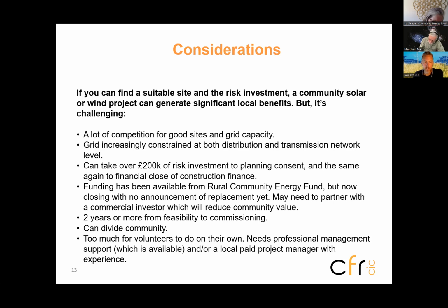There's a significant challenge in the way the grid queuing system works. If you're a community scale project connecting at 11,000 volts or 33,000 volts, you have to first go through the distribution application process and secure a connection, paying potentially a significant deposit to secure it. Only after you've accepted that connection does the distribution network operator - UKPN, Western Power, or SSEN - submit something called a statement of works to National Grid. National Grid will come back 90 days later and tell you whether there's a problem at National Grid level.